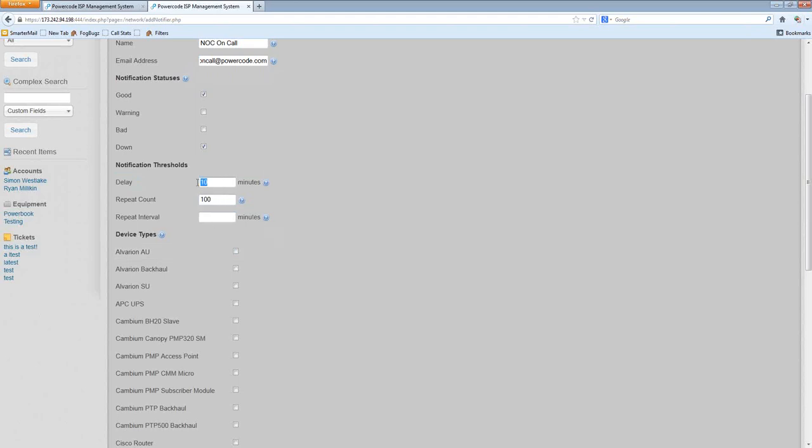So we have a delay of 10 minutes, so at this point something would have to be down for at least 10 minutes. We've got a repeat count of 100, and I'm going to say my repeat interval is 5. What this means is, after 10 minutes, send me a notification. Then as long as one of these selected statuses persists, continue to send me these notifications 5 minutes apart until 100 notifications have been sent.